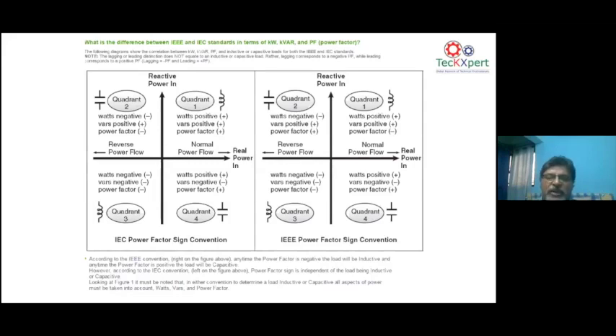So the function of a 4-quadrant operation is to ensure that the controller you're using is safely ensuring that the solar plant is not exporting reactive power, or rather, if it is importing reactive power, you are going to be penalized by TNEB. So you have to make sure this 4-quadrant operation is balanced correctly so that the regulatory requirements are met.